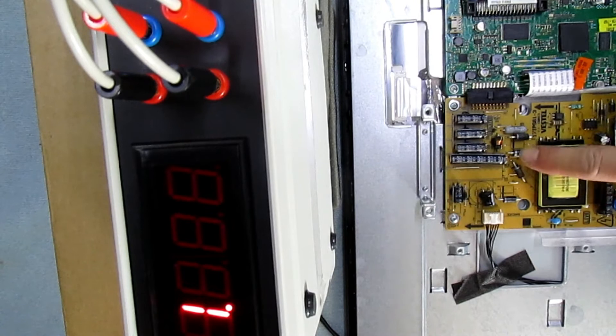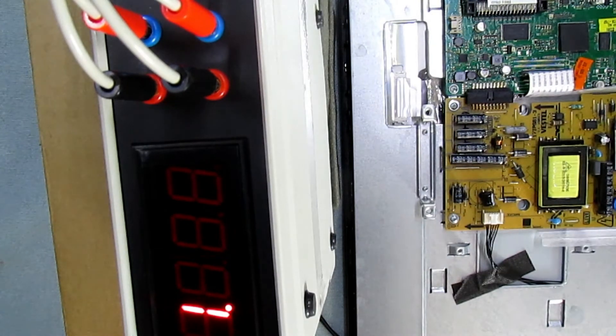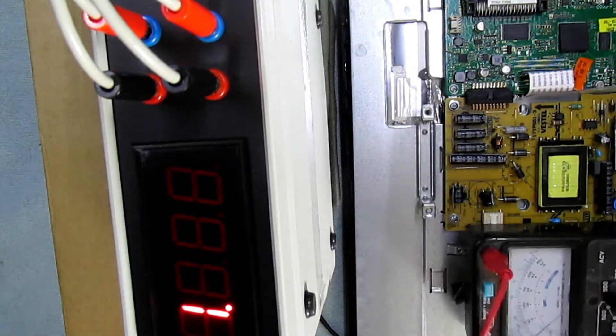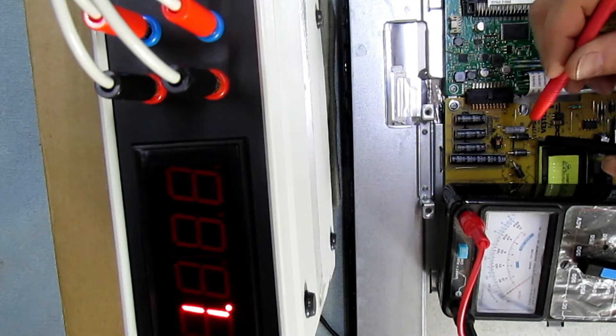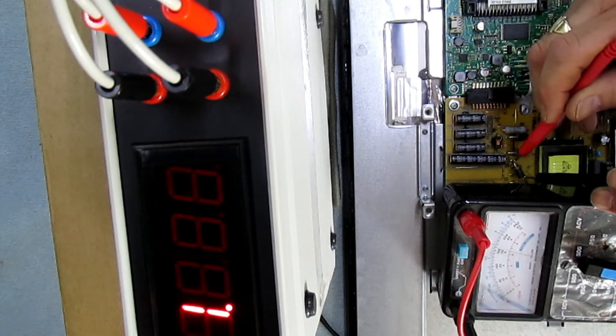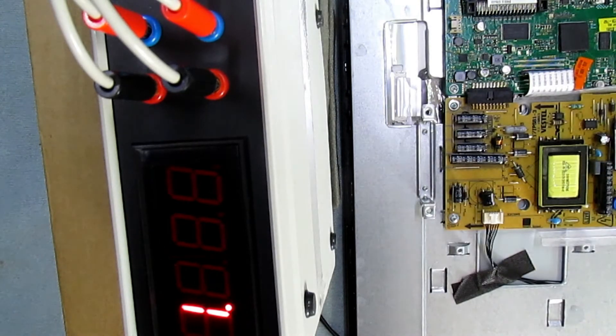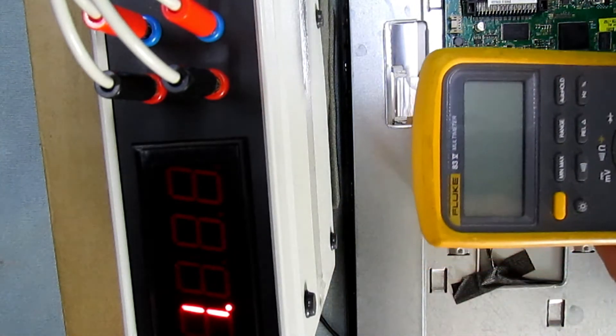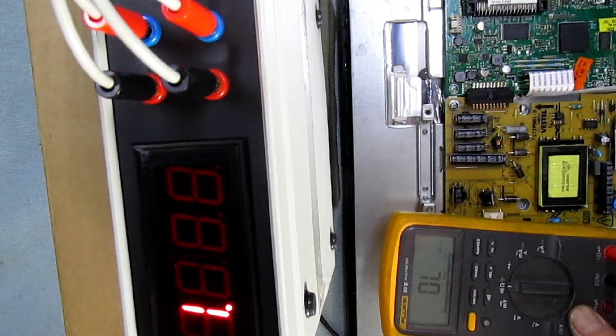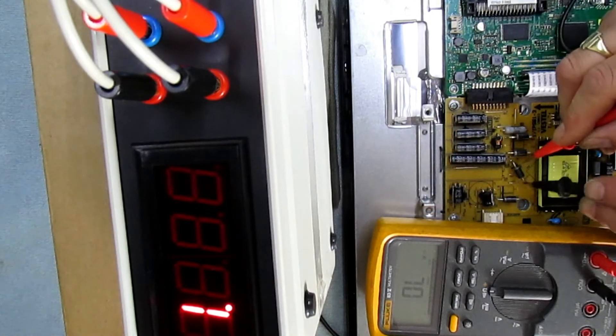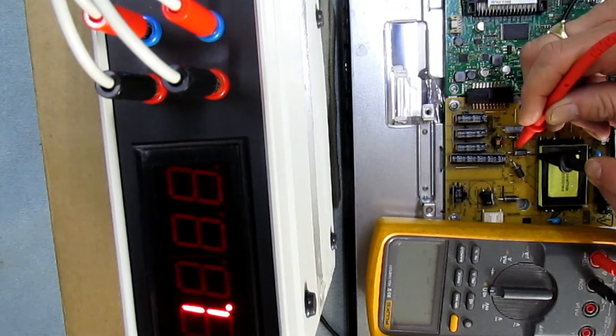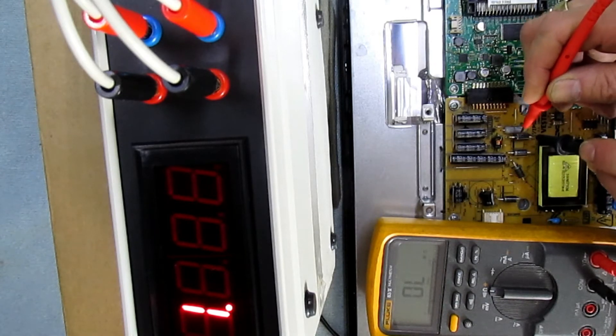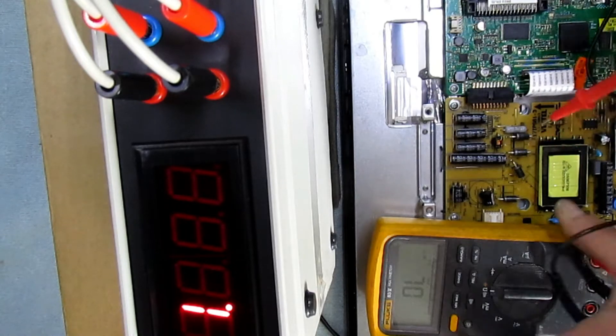Put the meter there so you can see, we've got short there, short there, short there. That's with an analog meter. For those of you who prefer to use a digital meter, I'll just show you on this one. Yeah, meter's in the camera so we've got dead short, that's short, that's short. Now these three diodes in parallel, but only one's faulty.